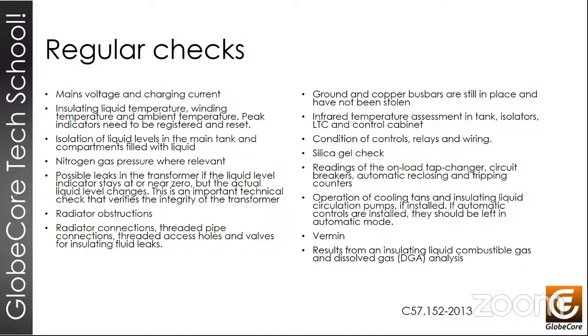What happens is that at this stage, in many cases, we can find weak points and vulnerabilities in our companies or organizations. And the fact is, when analyzing data and taking corrective action, the information we receive is oftentimes ignored. Sometimes people will perform oil analysis, electrical tests, inspect the transformer visually, and know what the conditions are. But when it comes to information, it's just stacked away in some folder, and that information becomes useless. So I recommend, if you are going to use the information and invest in oil analysis, then you must analyze the data you collect, because otherwise it's just numbers and they're useless by themselves. And then some corrective action must be taken.